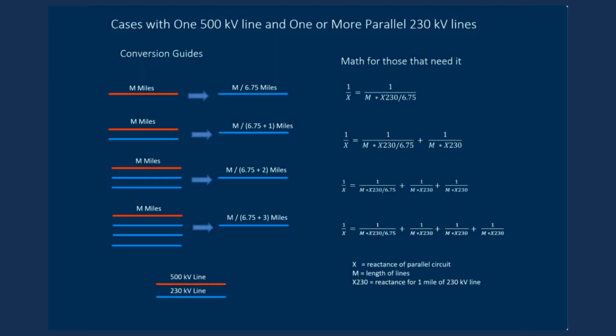In the case where we have a 500 kV line with one or more parallel 230 kV lines, then we simply divide by the 6.75 plus 1 if there's a single 230 in parallel, plus 2 if there's two 230s in parallel, and 3 if there's three 230s in parallel. The math for doing that is given on the right hand side here. I won't go through it, but those who want to see the proof can look at the equations here in detail.